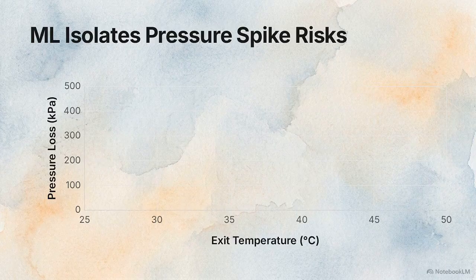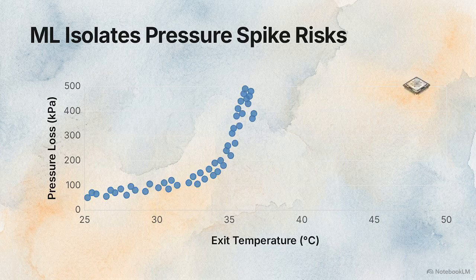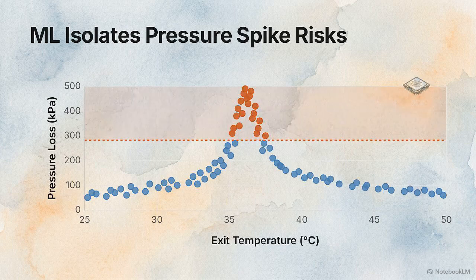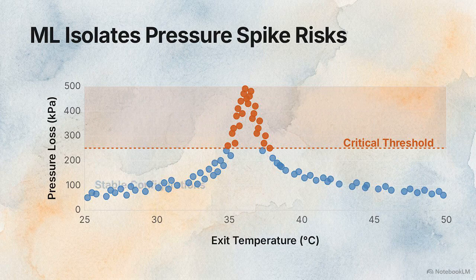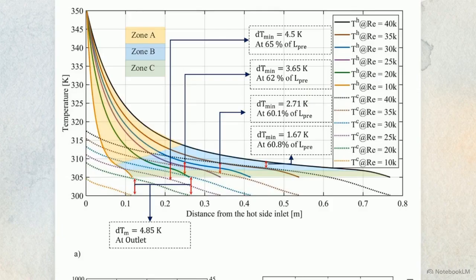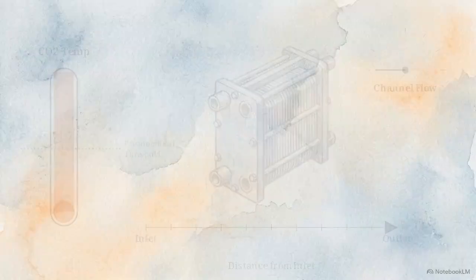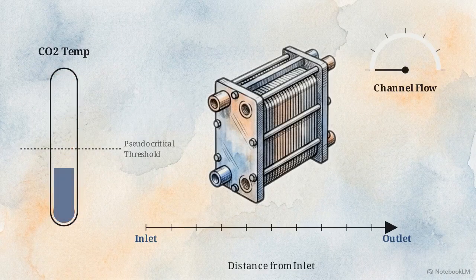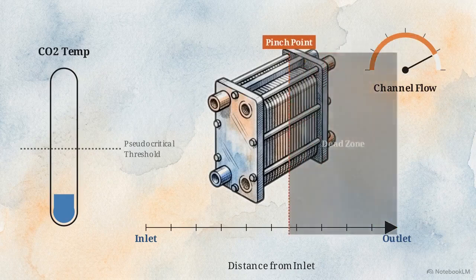Using the ML-driven analysis code, we can map exactly which parameter combinations cause those pressure losses to spike. Looking at these temperature profiles, we see that pressure losses are exceptionally sensitive to the targeted exit temperature and the mass flow rate through the channel. Pushing the exit temperature too far below the pseudo-critical mark or forcing the channel flow rate too high drives the pinch point deep inside the precooler.